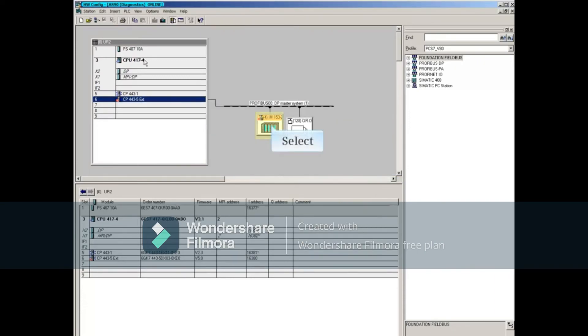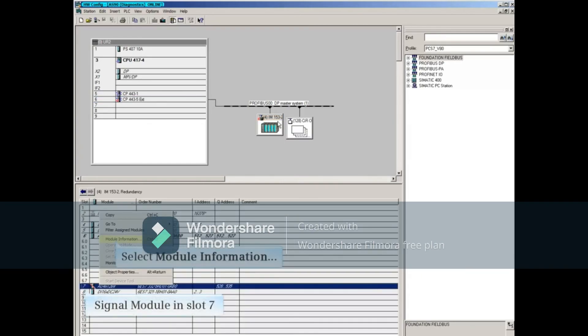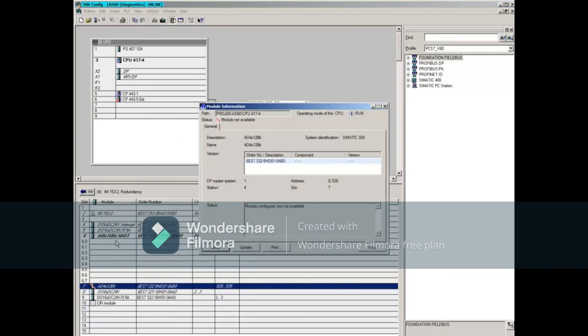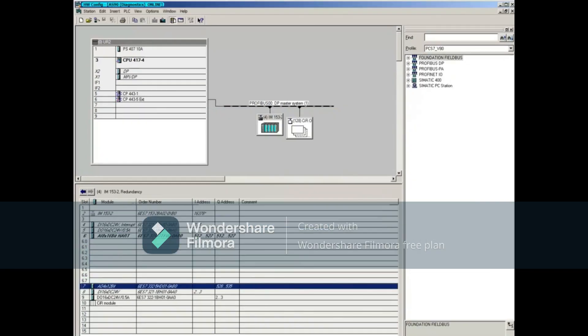Selecting the ET200M and opening the Module Information window of the signal module in slot 7 will show the problem, such as not available, wire break, and many others.